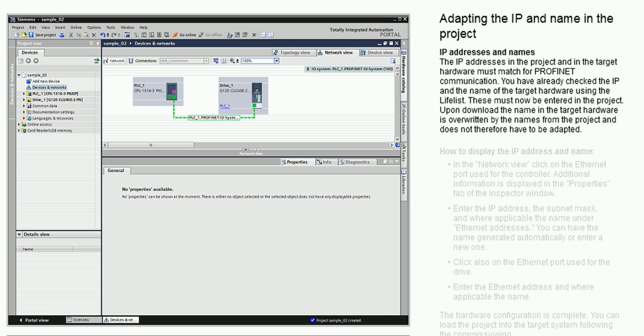IP addresses and names. The IP addresses in the project and in the target hardware must match for Profinet communication. You have already checked the IP and the name of the target hardware using the Lifelist. These must now be entered in the project. Upon download, the name in the target hardware is overwritten by the names from the project and does not therefore have to be adapted.